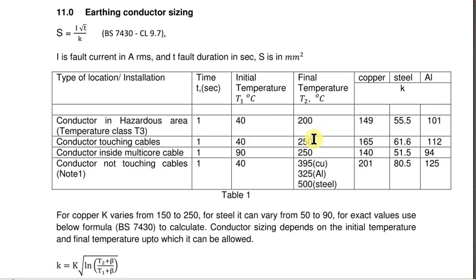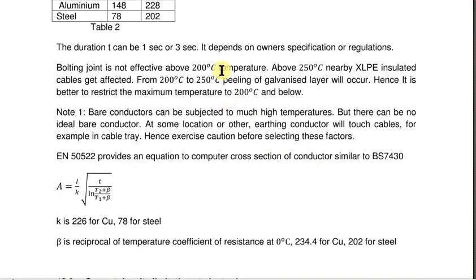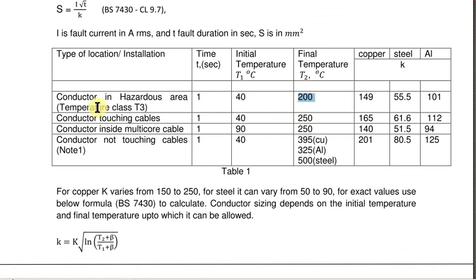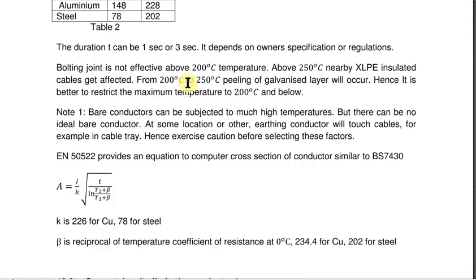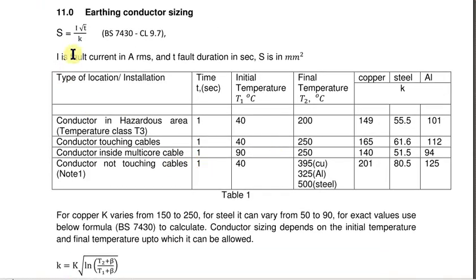One more thing: when you have joints, the joints become ineffective above a temperature of 200 degrees Celsius. So it is better to go for the first case, but if you feel that's very conservative, go for the second case. Also, when you use galvanized iron conductors between 200 to 250 degrees Celsius, dezincification of this galvanized layer occurs. So better restrict to 200 degrees Celsius.